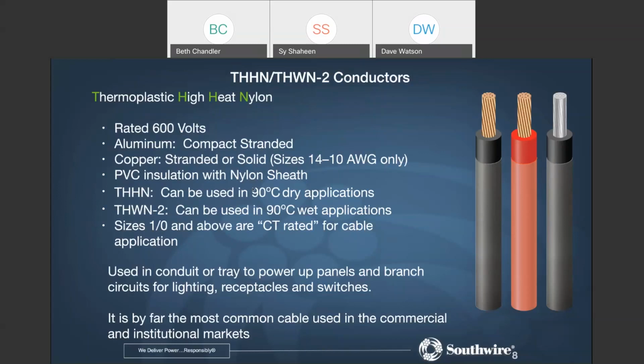It can still be compromised, though, when it goes through conduit edges. Let's say that you have a burr where a piece of conduit was cut, and that's sticking up, and then it gouges through the insulation. The nylon will give it some protection there, but it's not quite as rugged as, say, the crosslink product, the XHHW type of product. But the nylon sheath is there. Some people view it as sacrificial, meaning it's there to take the damage to protect that underlying PVC insulation. So if the PVC insulation is undamaged, then you still have all of the characteristics that you need, except for one little difference. The PVC insulation alone provides the electrical requirements. It also will be sunlight resistant for the size range that is sunlight resistant. The nylon does provide a little bit extra gas and oil resistance compared to the PVC alone. It's a small difference, but there is a little bit of an impact there.